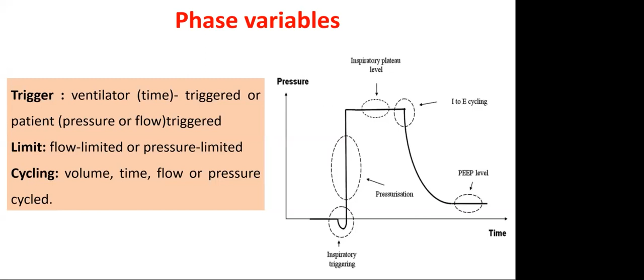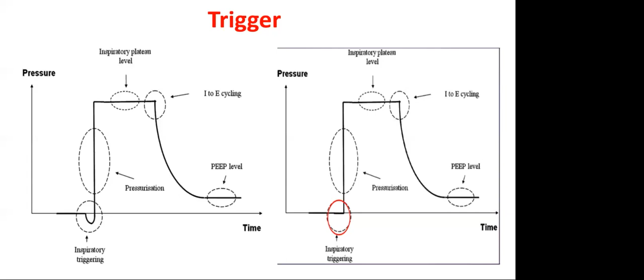Whether it's patient triggered, you can see a negative deflection in the pressure scalar. If it's machine triggered, you won't see anything. And how much limit it can be, that can be either pressure limit or flow limit. And when it is cycling from inspiration to expiration, that also depends on your I time. So these are the three variables: trigger, limit, cycling.